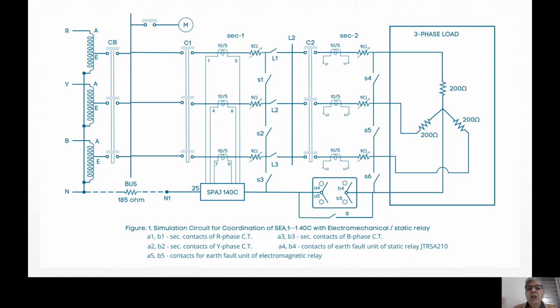Why a third contactor? Because I have simulated a three-phase, two-section radial feeder. The first section is controlled by the relay SPAJ, and the second section is controlled by the conventional electromagnetic or static relay. I have wired it in such a way that I can go for a static relay also, I can go for an electromagnetic relay also. At terminals A1 and B1, section 2, I will connect the electromechanical type relay, or otherwise I will connect the static relay. You see, I can connect any relay I like.